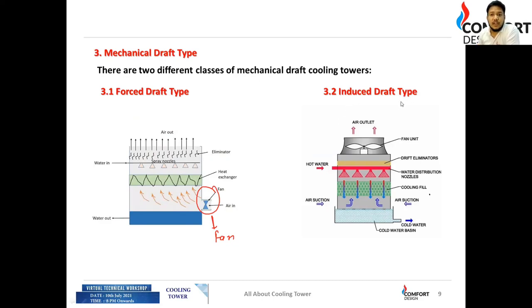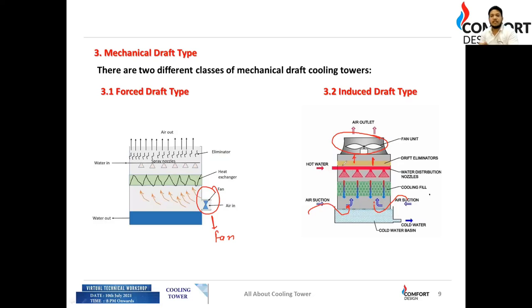In an induced draft cooling tower, the fan is placed at the top. To throw air outward, it sucks air from inside the tower. Air suction occurs from the sides. Hot water is drizzled from the top, and during contact, the air takes the heat from the water. The water temperature drops, it accumulates at the bottom, and the hot air is released into the atmosphere.